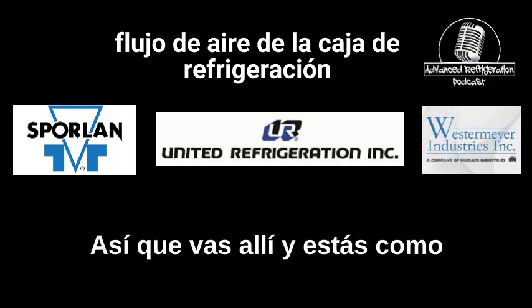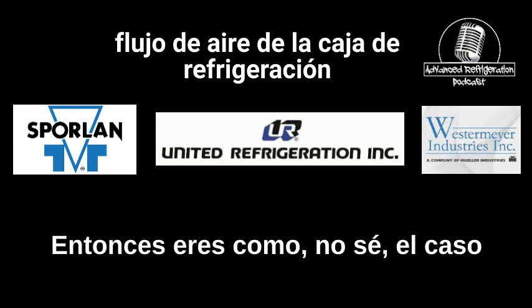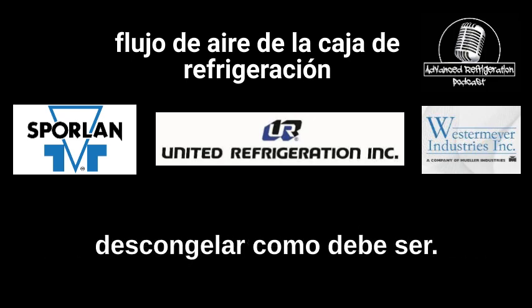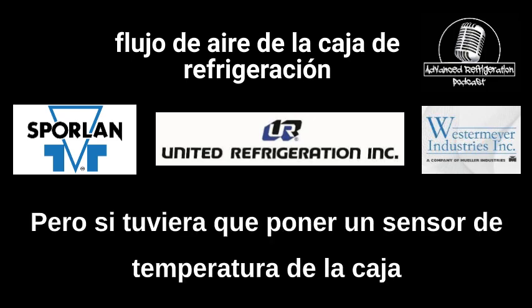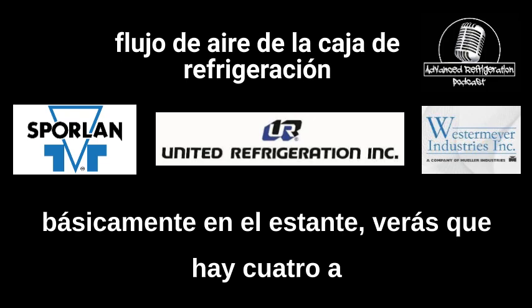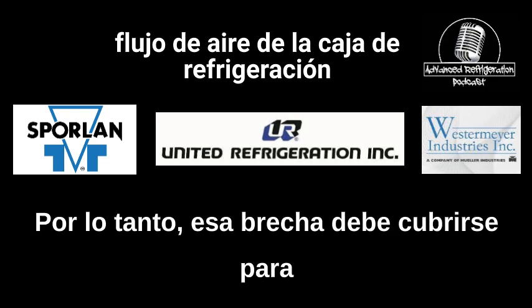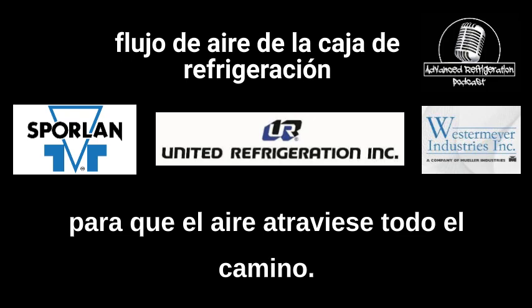So you go there and you're like, oh, the case is pulling down temperature. It's going into defrost the way it should. Everything seems fine. But if you put a case temperature sensor on the shelf, you'll see there's a 4 to 6 degree variance versus the discharge air. So that gap needs to be covered up in order for the air to go all the way across.